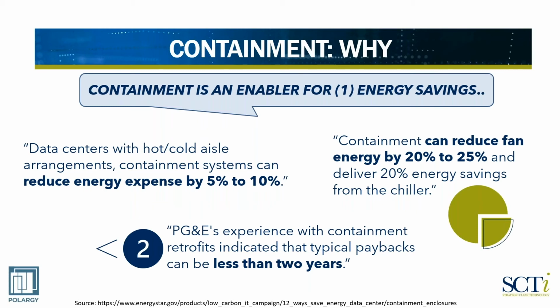The why: a big point is the fact that you can have significant energy savings. Now, these are some stats out of Energy Star last year. Basically, they're saying if you do hot aisle, cold aisle containment, you'll reduce cooling energy expense by 5 to 10%. Containment can reduce energy consumption 20 to 25% and deliver a 20% energy savings from a chiller.